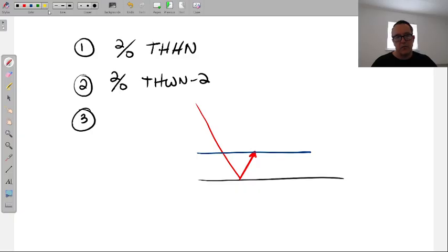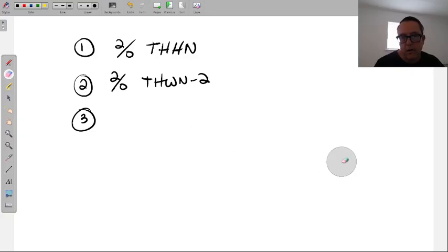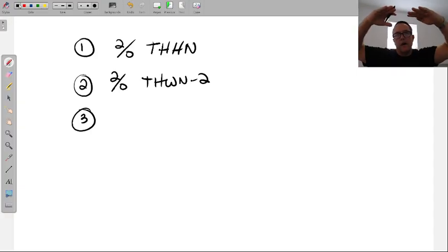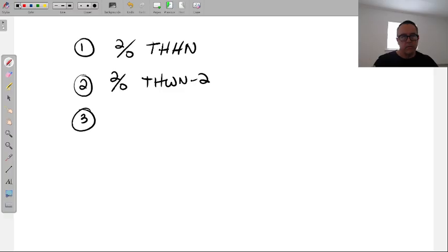Not too critical. I would rather you just understand correction factors and how to apply them. So if you ever get a chance to go on a rooftop, which you very likely will if you work in this industry, you'll notice that all the conduits on the rooftop are not laying on the roof. They're up off of the roof itself by a little bit.